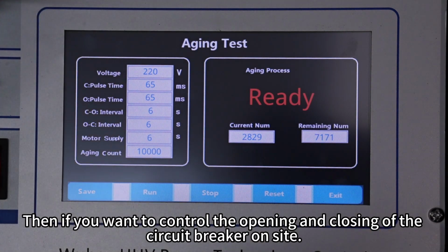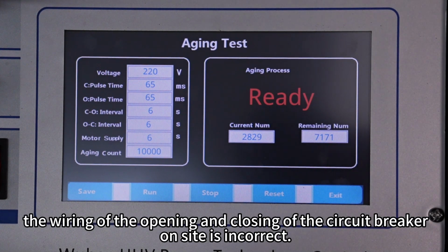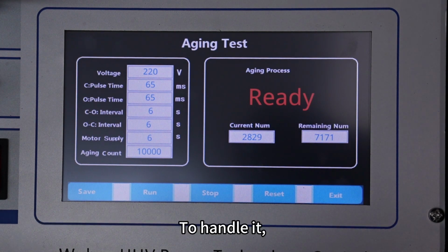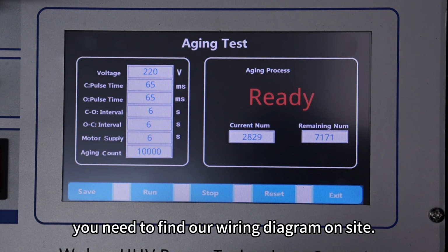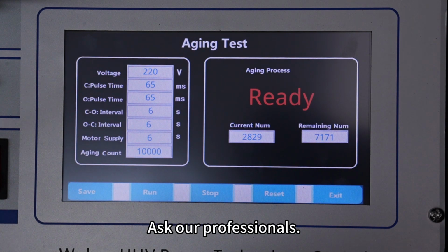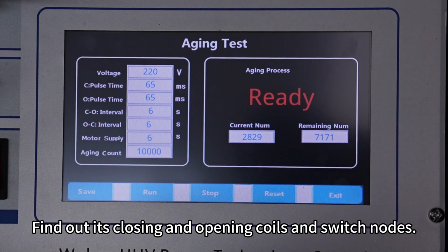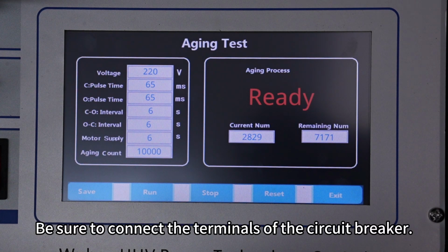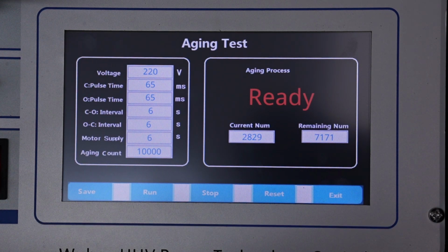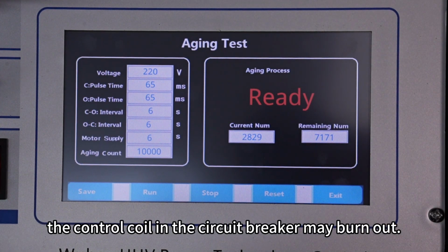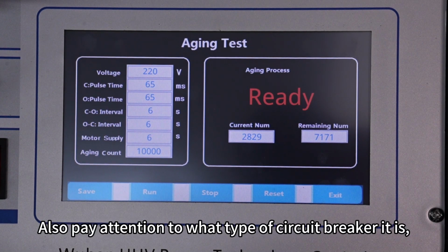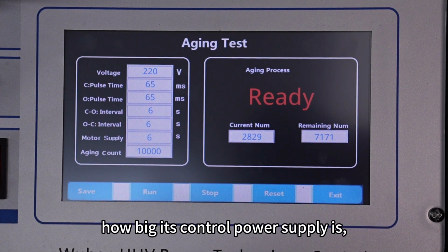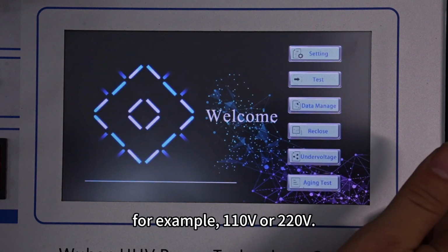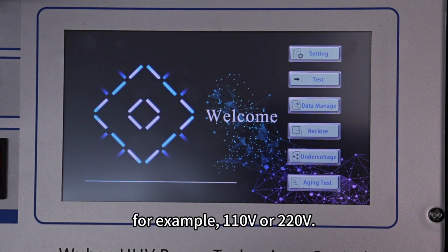Then if you want to control the opening and closing of the circuit breaker on site, and its switch does not work, the wiring of the opening and closing of the circuit breaker on site is incorrect. To handle it, you need to find our wiring diagram on site. Ask our professionals. Find out its closing and opening coils and switch nodes. Be sure to connect the terminals of the circuit breaker. Otherwise, the control coil in the circuit breaker may burn out. Also pay attention to what type of circuit breaker it is, how big its control power supply is, for example, 110 volts or 220 volts.